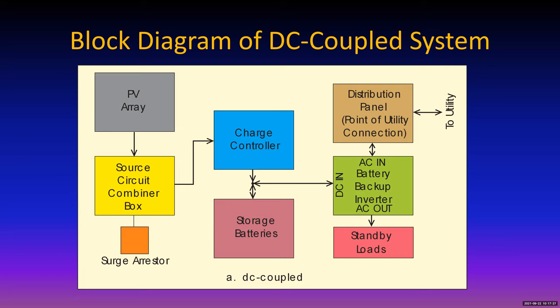And in fact, this is the way most of these systems operate pretty much all the time, except when there's a utility outage. So once the batteries are charged, and you can see the bidirectional character of the arrows there, that's the power flows. And so power only flows from the PV array to the source circuit combiner box. It only flows into the charge controller. It only comes out of the charge controller, but the battery's energy can go in or out either way. And the same is true with the battery backup inverter.